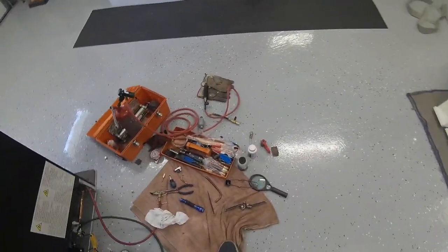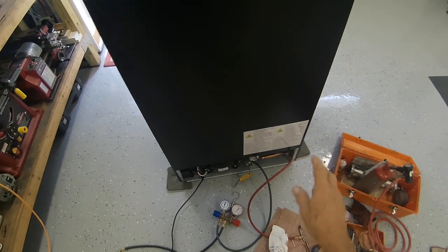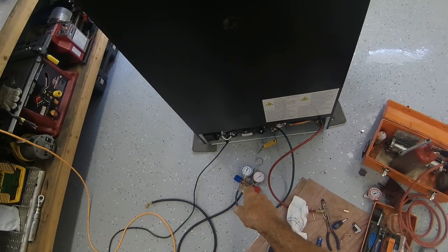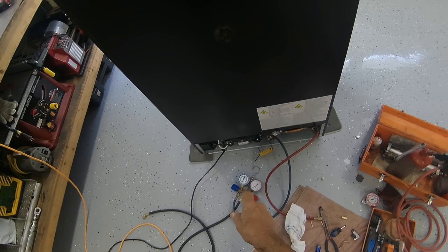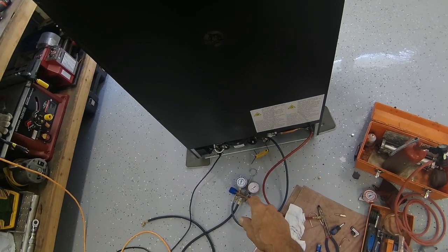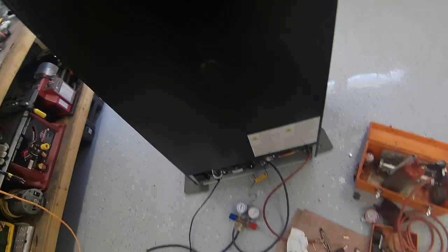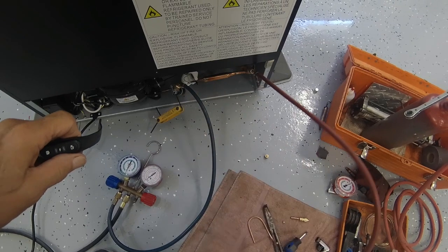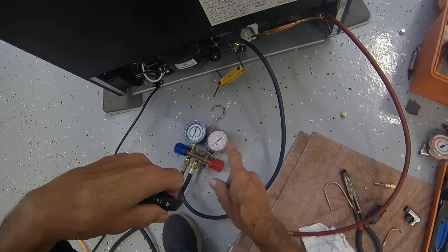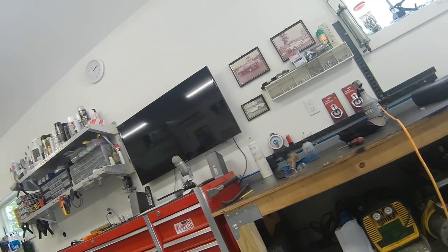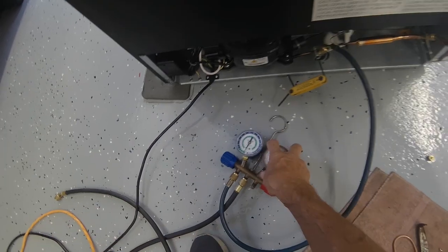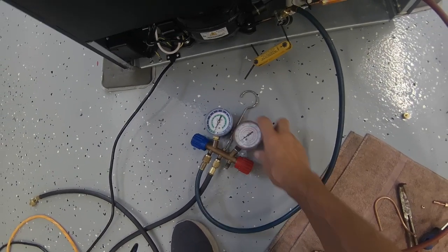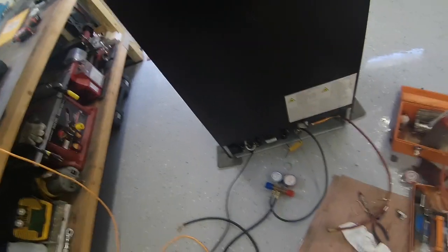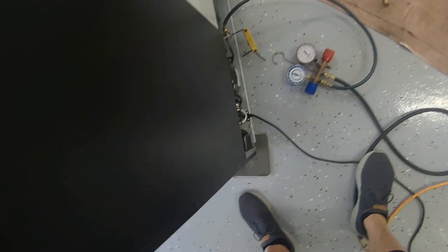Here's an update. This morning I came in after letting it run overnight. The low side pressure was at 25 inches vacuum, and when I left last night it was 29. So I put a discharge hose on the filter dryer, and some Freon came out. Now it's been running since this morning, for about 6 more hours. It's still down to about 29 inches vacuum, but I still hear gurgling sounds in the evaporator.